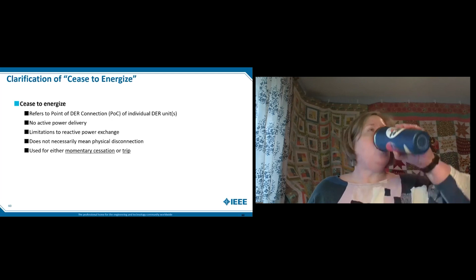Versus, I leveraged doing the 1547-2018 with another developer in the hopes that we can avoid adding a voltage regulator to a high penetration feeder. This is a great example where DER can actually bring a solution that works on both sides of the meter, so to speak. But there are regulatory and commercial barriers that have to be overcome.